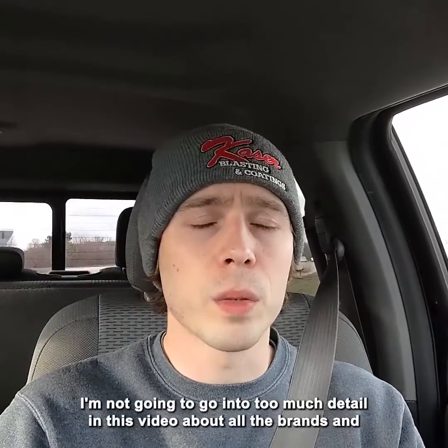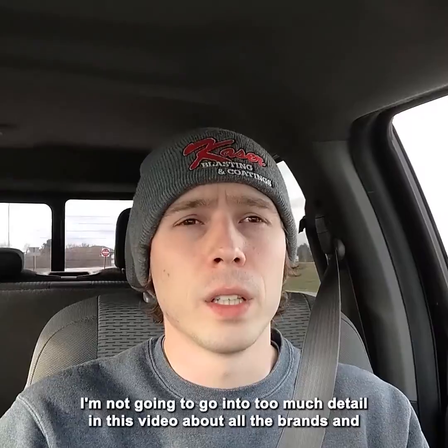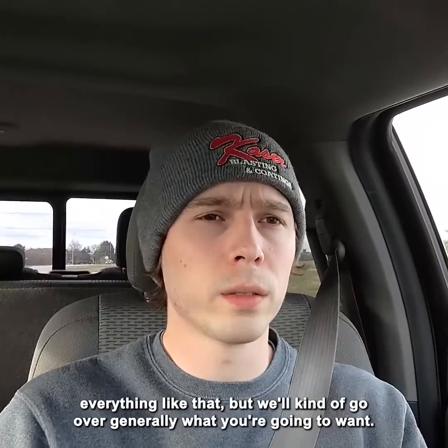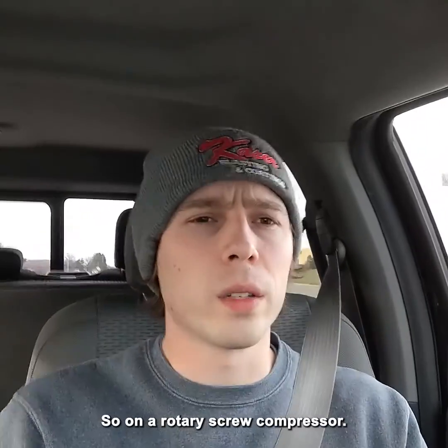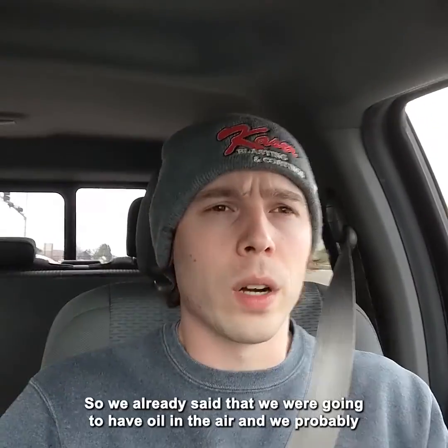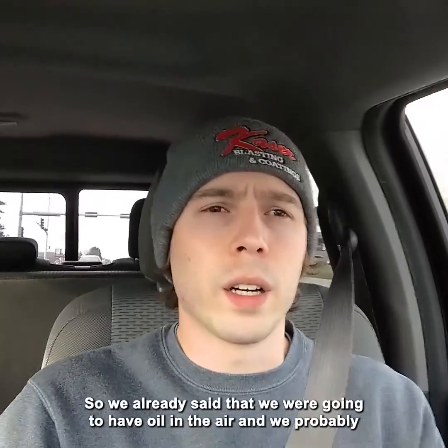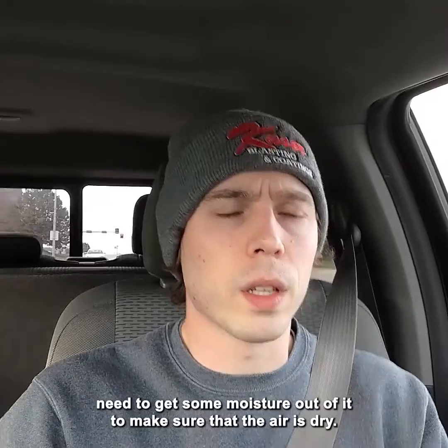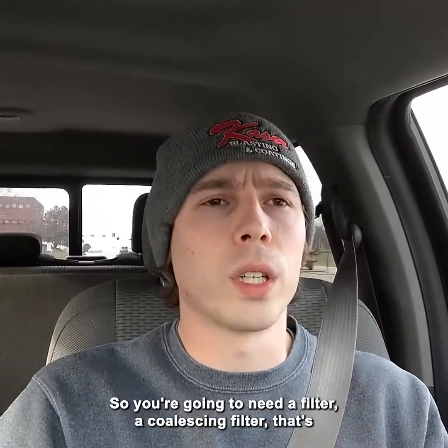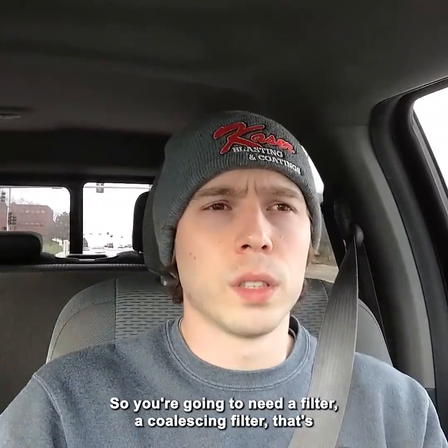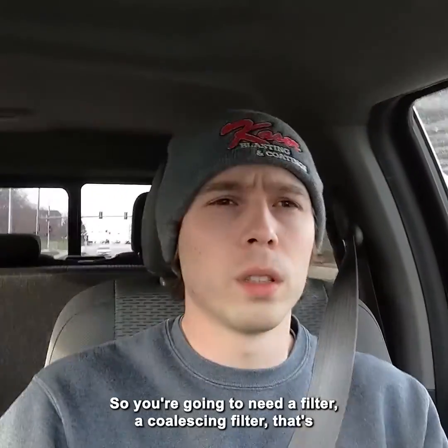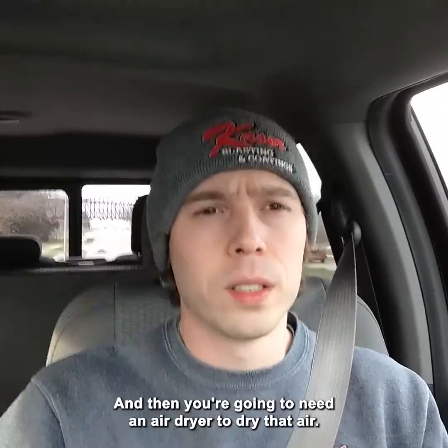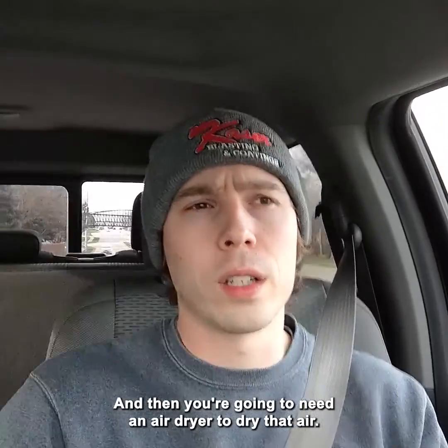I'm not going to go into too much detail in this video about all the brands and everything like that, but we'll go over generally what you're going to want. So on a rotary screw compressor, we already said that we're going to have oil in the air, and we probably need to get some moisture out of it to make sure that the air is dry. So you're going to need a coalescing filter that's going to help you get oil out. And then you're going to need an air dryer to dry that air.